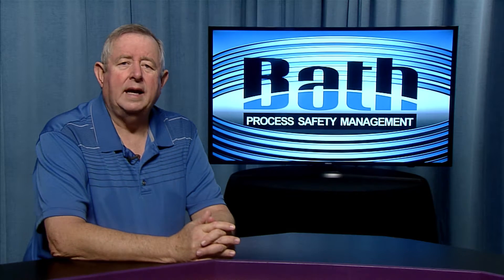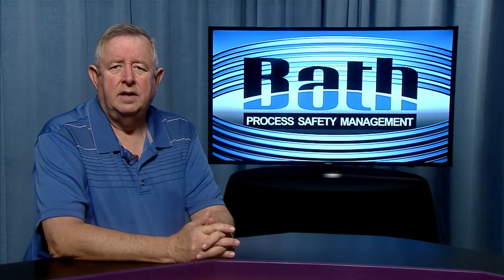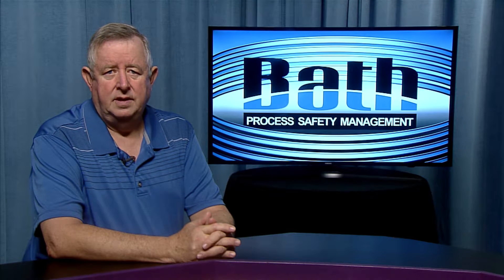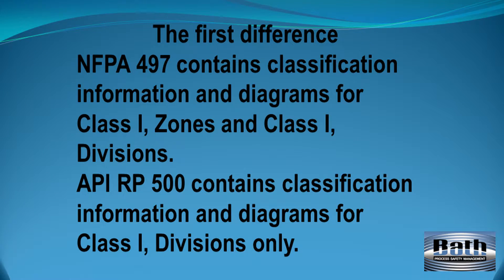The first difference is that NFPA-497 contains classification information and diagrams for Class I zones and Class I divisions, whereas API-RP500 contains classification information and diagrams for Class I divisions only.